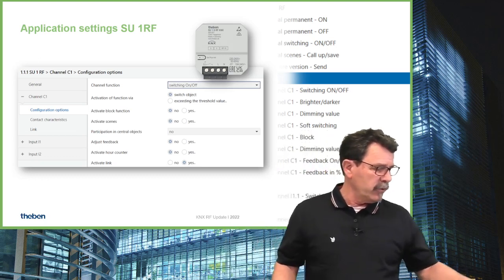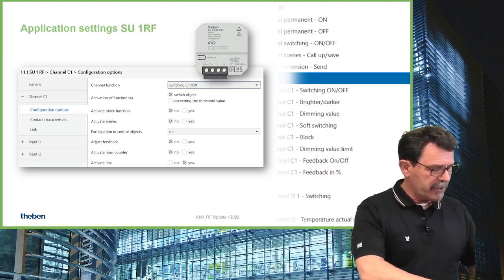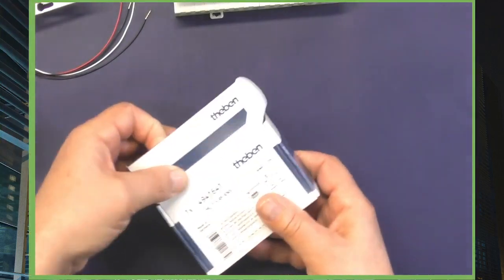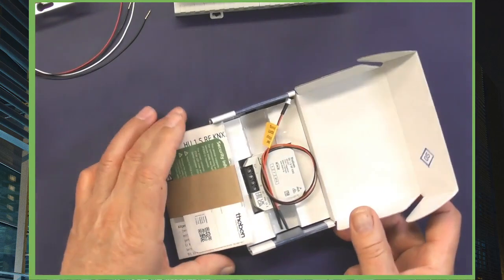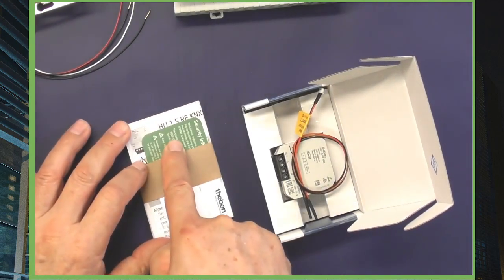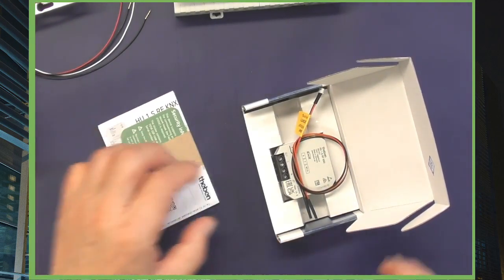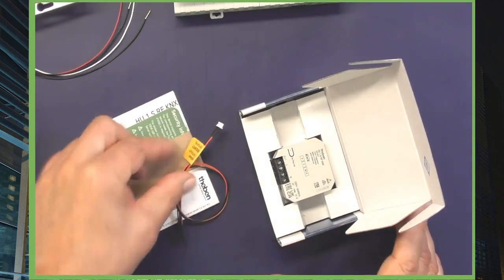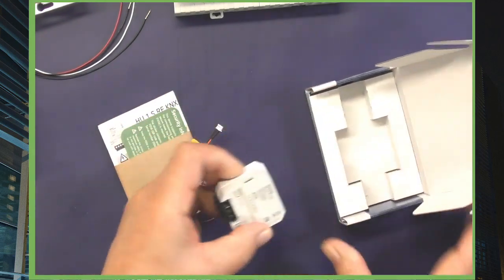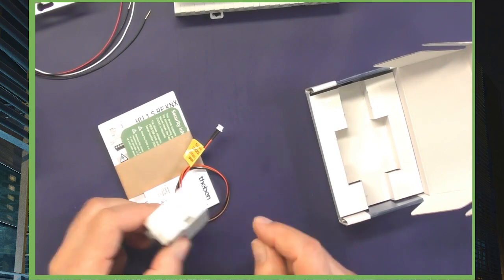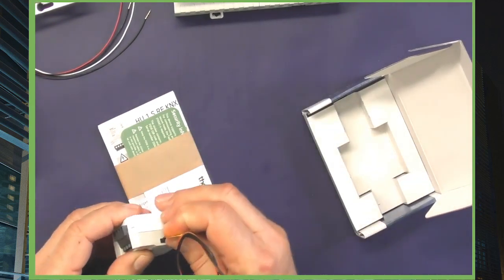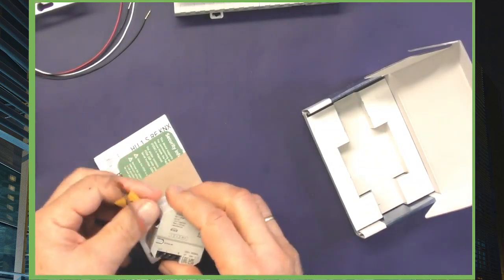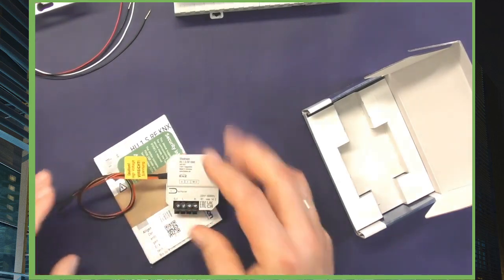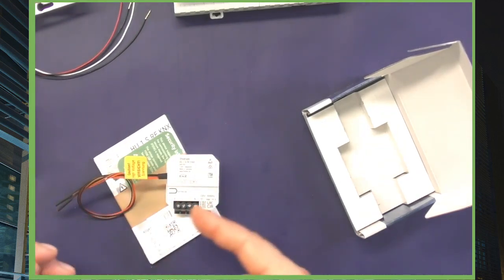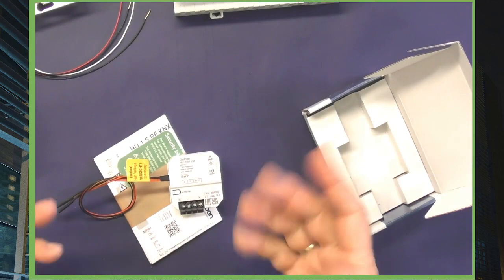So that means we do have here - if I unbox, for instance, our original new actuator - you find here the security card with a reasonable FDSK code. You find here a binary input cable, and here you discover on that side we have the interface - you just plug it in, wrong side. So you have here two binary inputs, here you apply 230 volt, and that's it.